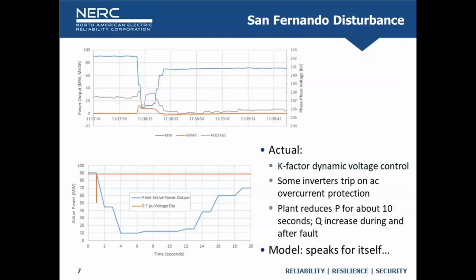We know it was a 2.5 cycle, 3-phase normally cleared fault. So voltages should recover back to acceptable conditions at the POI, at least around that time frame, if not a couple cycles longer, but definitely not 10, 15 seconds. So there's obviously a clear difference here between the orange and the blue, and it's not a matter of do these squiggles look close enough—they don't even remotely match each other.